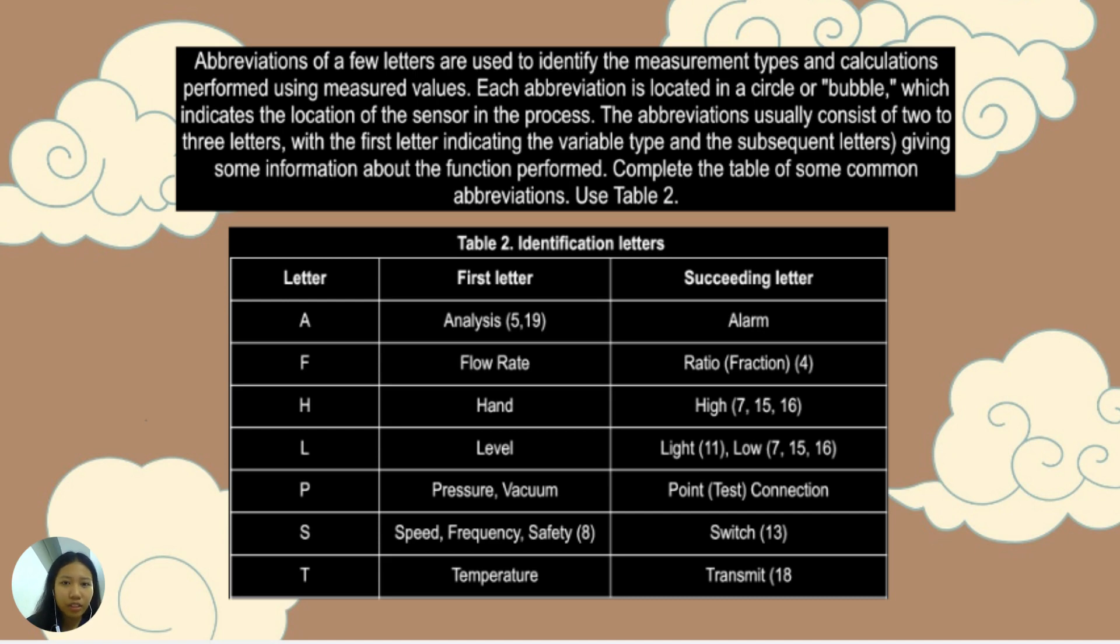For the second topic of the activity, which is the identification letters. Abbreviation of a few letters are used to identify the measurement types and calculations performed using measured values. Each abbreviation is located in a circle or bubble, which indicates the location of the sensor in the process. The abbreviations usually consist of two to three letters with the first letter indicating the variable type and the subsequent letters giving some information about the function performed.